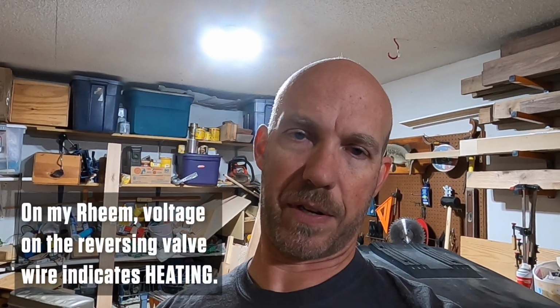We have to figure out: number one, I'm expecting voltage on the white wire, since that's the auxiliary heat bringing on the heat elements. I'm also expecting the yellow wire, which tells the outside compressor to come on, to be energized, because whether it's heat or cool, that's going to be on. In my case, I shouldn't get voltage on the reversing valve wire, because that's how mine works—yours might be the opposite. And obviously the fan wire should have voltage, telling the fan to come on and circulate air in the house.